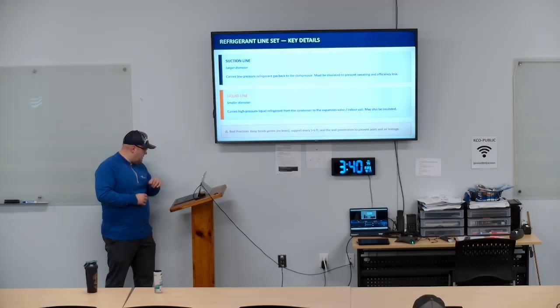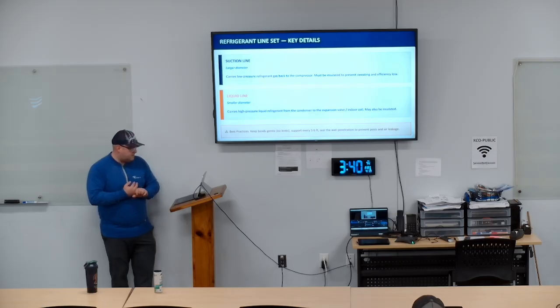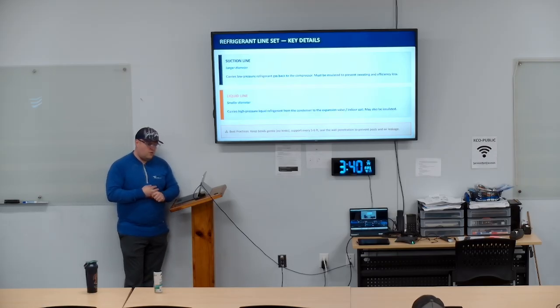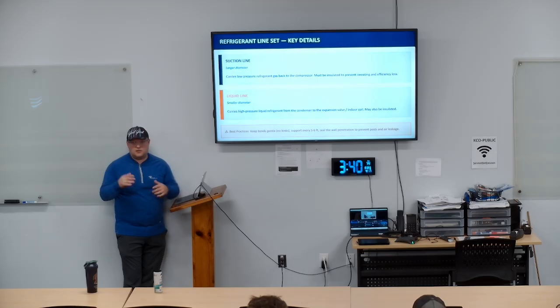All right. Line set, key details. Suction line is always the larger line. Liquid line smaller. Suction line is carrying low pressure refrigerant. It always needs to be insulated. Suction's always insulated. Doesn't matter what system we install, suction's insulated.